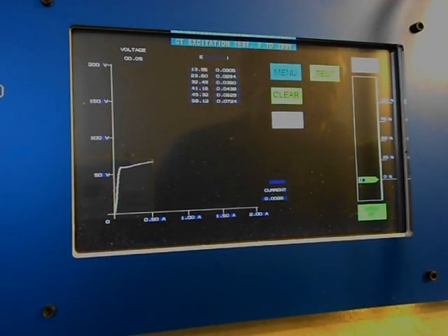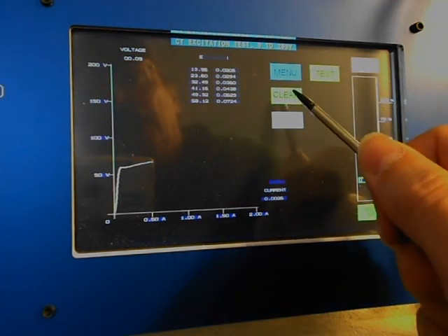I can now fill in the heading if I wanted, the substation, all that sort of thing, and my data sheet is complete. I have another CT to test.